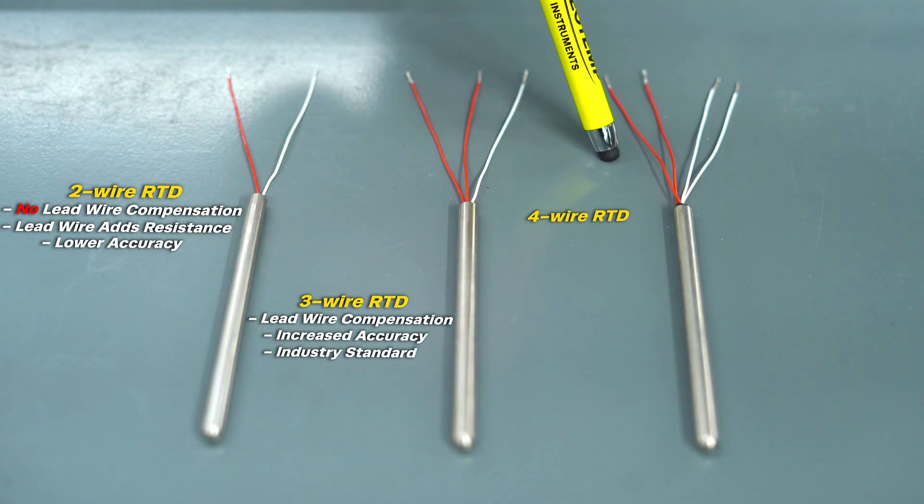A four wire RTD fully isolates the resistance of the RTD element from the resistance of the lead wire, and it's recommended for applications requiring the highest accuracy.